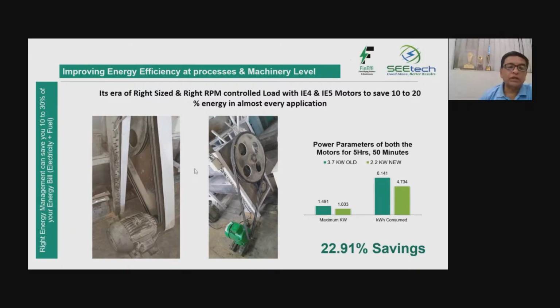So here you see the old motor is replaced by an IE4 motor. We were hoping to get savings of around 15%, but we actually got savings of around 23%. This is the kilowatt consumption before and after, and this is the maximum kilowatt drawn in the before and after scenario. The old motor was 3.7 kilowatt, and we had to replace it because it was underloaded, inefficient, and had been rewound.